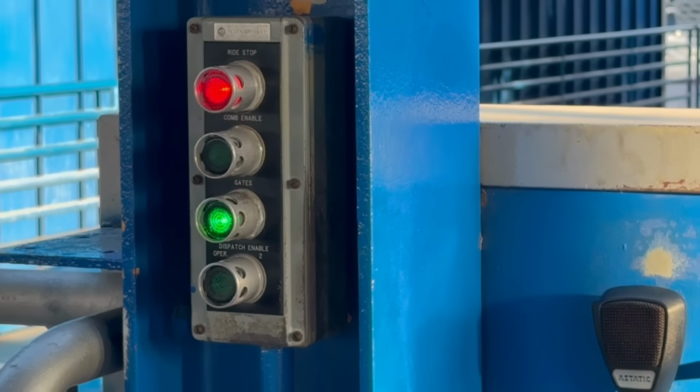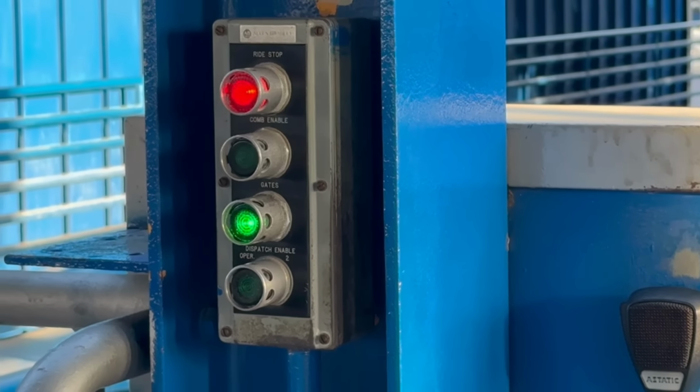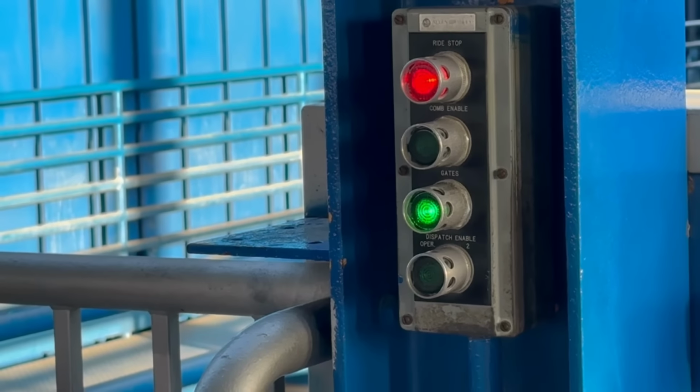Like if I switch the ride into manual mode, or my buddy switches the ride into manual mode, and I say, I need to go out and watch those brakes work. Maybe the brakes are remote and I can't quite see them, but I don't want a train running through there. So my buddy watches the panel, he keeps it in manual mode, I walk out to the brake segment and I go up to that momentary operation button on the maintenance panel, and I push that button in, and when I push that button in, all those brakes open up.